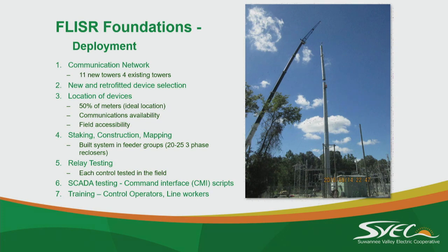We sent guys out in the field. We bypassed our reclosers and made a fake fault. We let SCADA pretend it was a real auto deal. The guy's sitting at the midpoint, it opens. We got a 2-way feed, it closes. Hey, this is good, that's what we want to see.